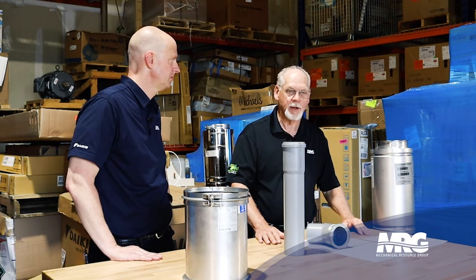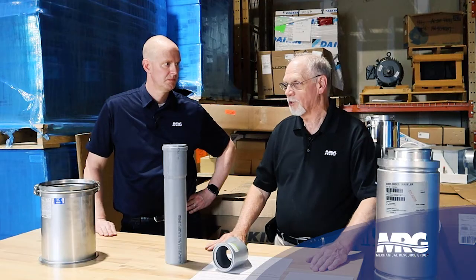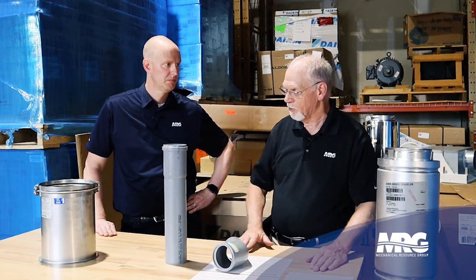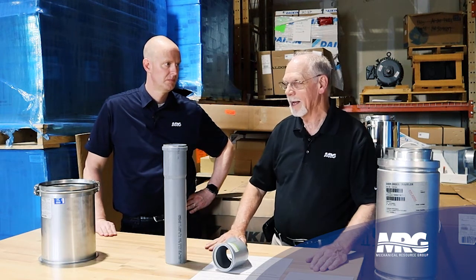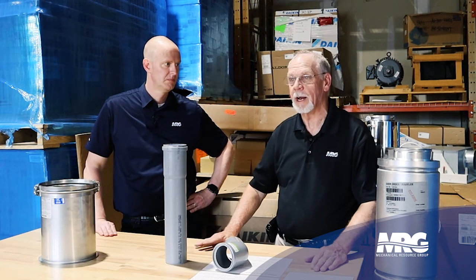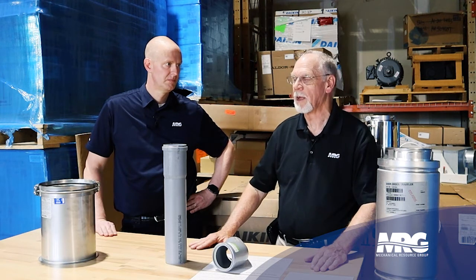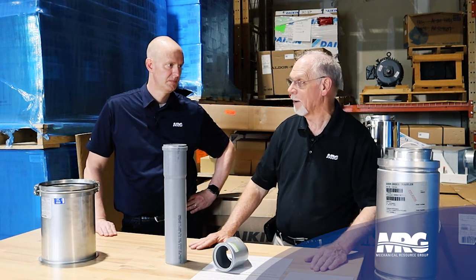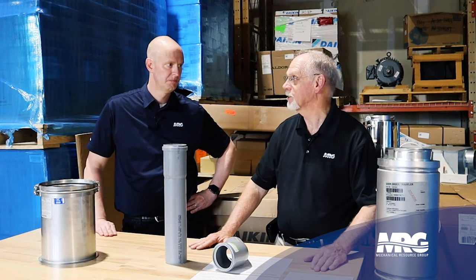based on the manufacturer's equipment, you may have a fan assist, because as this flue gas leaves the appliance, as it gets further out, it's going to cool down. It can get cool enough that it doesn't move. So sometimes we need a fan assist to get that on out. And sometimes the fan will push and sometimes the fan will pull. It just depends on what the application is. But it can do either one.